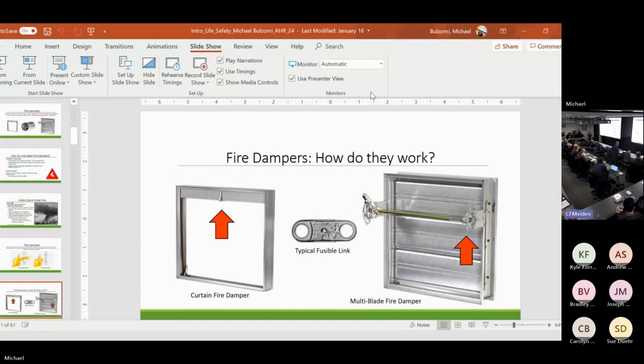If there is airflow in the ductwork, you need an assist. Gravity is not enough to overcome velocity and pressure, so we put a spring on it. That spring actually pulls the damper down as well. I already explained to you on the multi-blade, I got a fusible link here, it melts, that damper slams shut. The difference between the two, nothing. They do the same thing.